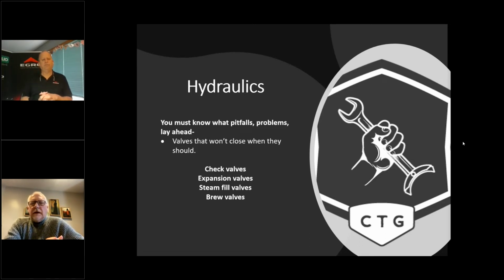Now the thing about the check valve is it doesn't have to be after the flow meter. The check valve can be even before the machine. The whole idea is to have a column of water that can't move backwards in the water circuit. So long as that's functioning, then heat exchanger water, or water from the boiler if you're running a dual boiler system, can't push against that check valve, even if it's at the very beginning of the machine. So that's why check valves are kind of important. And then the expansion valve has to be between that check valve and the rest of the machine, so that the expansion valve can do its job.